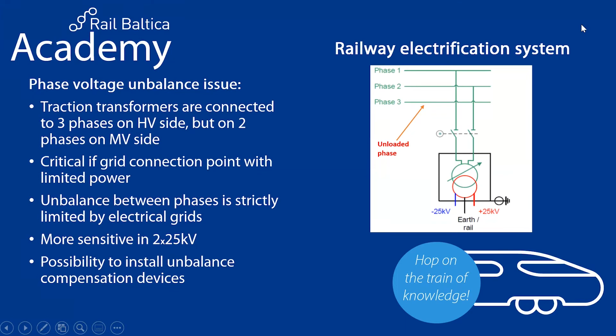This unbalance problem is more sensitive in 2 times 25 systems, because we have more powerful substations in 2 times 25 to power longer sections. There are different solutions to this: one is to install an unbalance compensation device, an active system that is one of the possibilities, but it should be analyzed case by case.